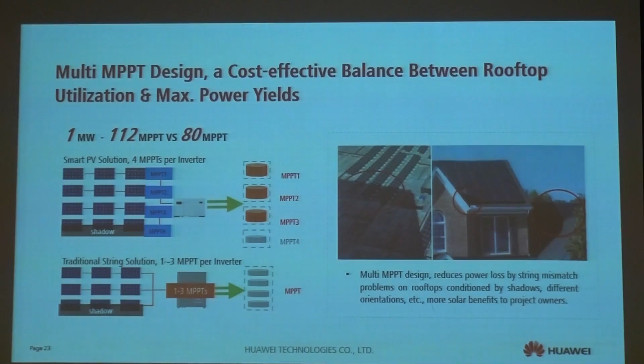For this part, we take natural cooling, low fusing designs, because all our inverters' panels connect directly. Most importantly, we have more MPPTs, but each MPPT only uses 2 strings. So if there's a short circuit, the reverse current for one MPPT will be less than 10 amperes, which is still within the safety range of the panels. So in this case, we don't need internal fuses for protection.